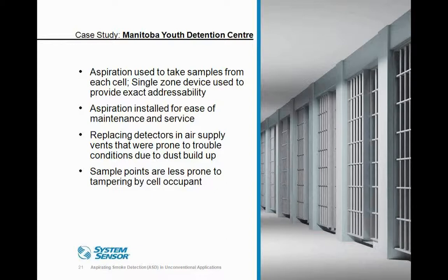They also replaced detectors in the air supply vents that were prone to trouble conditions due to dust buildup in this environment. So that's another issue that FAAST addressed in this application in the detention center.